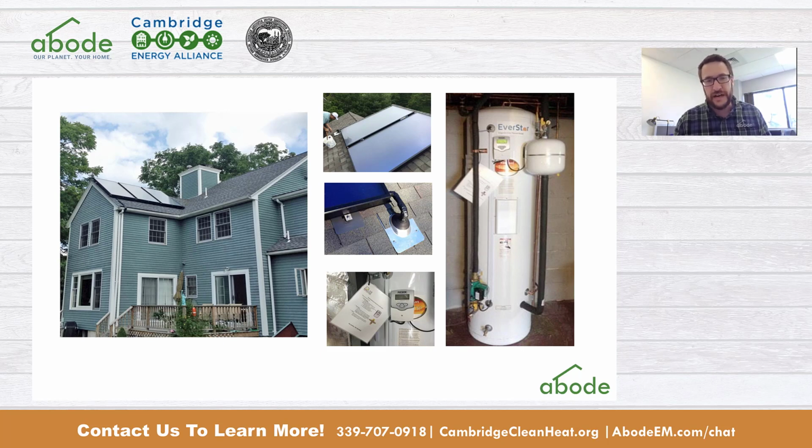However, in the winter time, when the sun's not shining, these panels aren't going to be producing that much. If it's a very cloudy day, they're still going to be producing, but likely not anywhere close to 100%. So when you're thinking about this type of traditional system, you are thinking about what you are going to use to make up the rest of the energy. Most of these systems do have an electric coil built in, but some other types of systems can integrate seamlessly into an existing hydronic system. If there's a boiler already in the basement, it's not mechanically complicated to add an additional zone that can make up the difference on this solar hot water system.